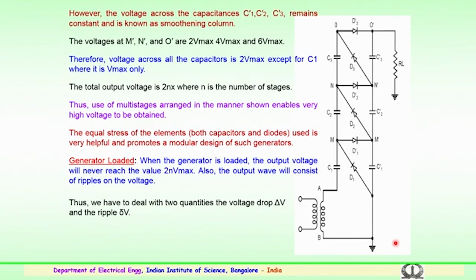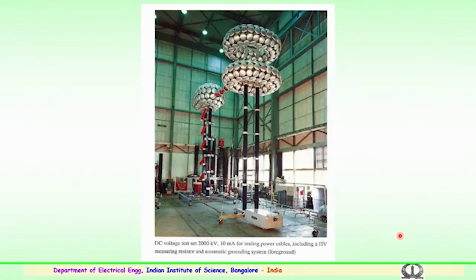These are the basic ideas of generating high voltage DC, and several high voltage DC sets are available across the country. One example is a DC test setup with a capability of 2000 kilovolts and current rating of 10 milliamps, used particularly for testing power cables, including a high voltage resistor, automatic grounding system, and so on. This shows a photograph of a high voltage DC set in a laboratory.